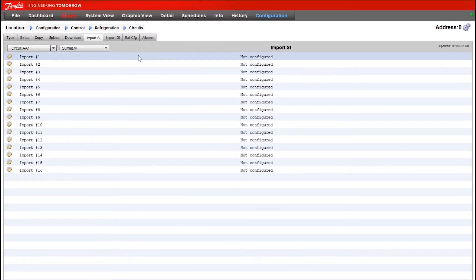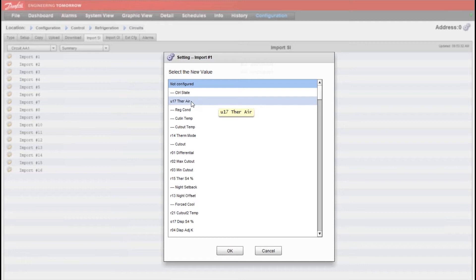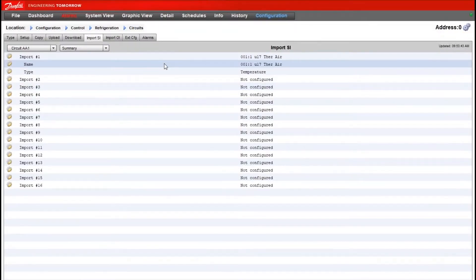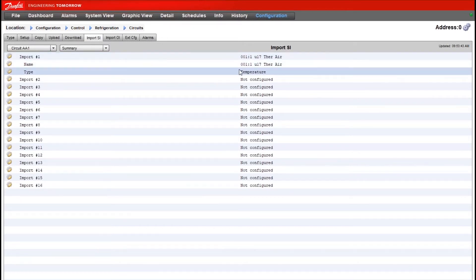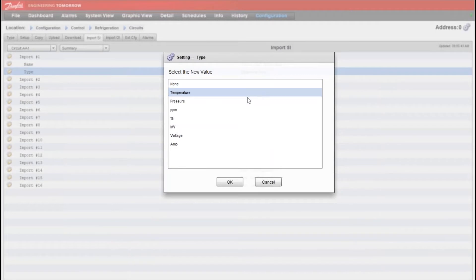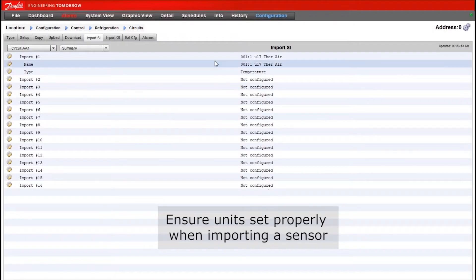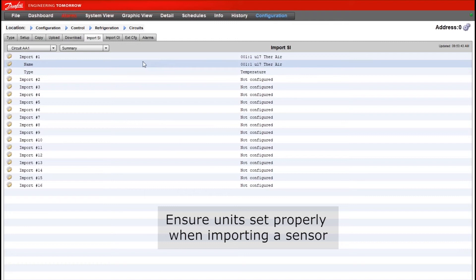You can see up to 16 sensor points can be imported from each case controller. Just to show you as an example, if I wanted to import the main sensor value from the case controller here I can choose that value from the list. And then you also have to make sure the type is configured properly. So if I tried to import a pressure transducer I would need to make sure I'm changing the type to pressure afterwards or else it would show up with the wrong units later on in the calculation.